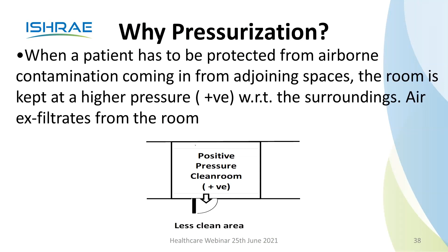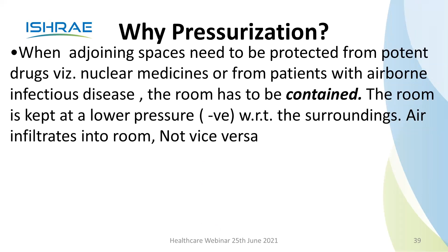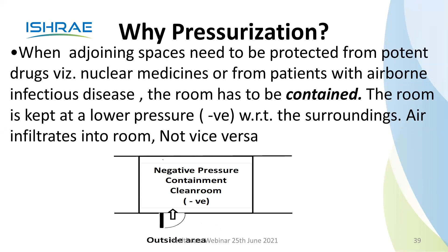When the adjoining spaces need to be protected from potent drugs, nuclear medicine, or patients with airborne infectious diseases, the room has to be contained. That means the room air should not go out. Outside air can come in. The room is kept at negative pressure. So here you will find that air can only come in, not go out. In today's context, COVID patients are kept at negative pressure, for example. The convention is to have a differential pressure of at least 2.5 pascals. That means when we say there is a pressure difference, it should be measured at least 2.5 pascals.